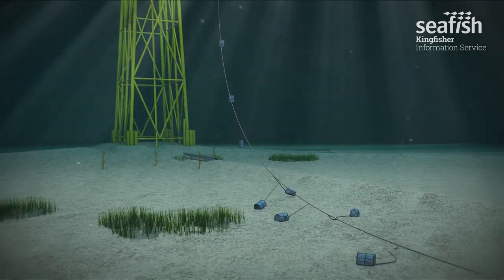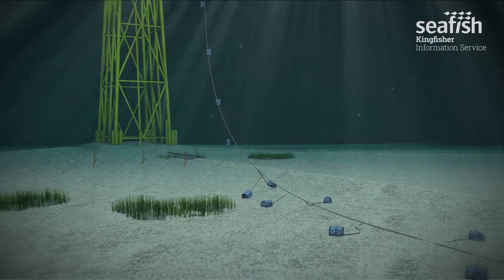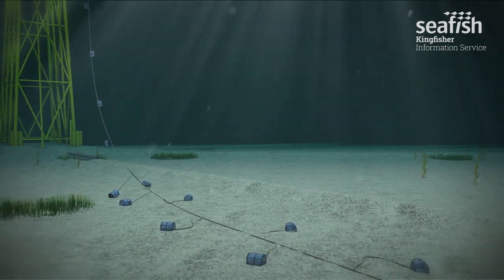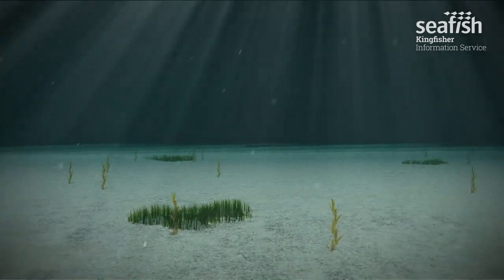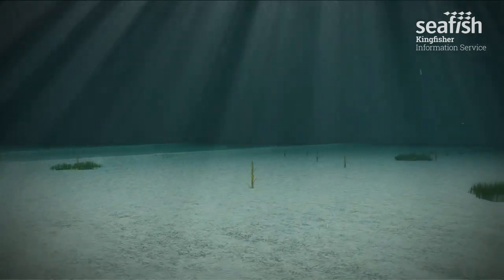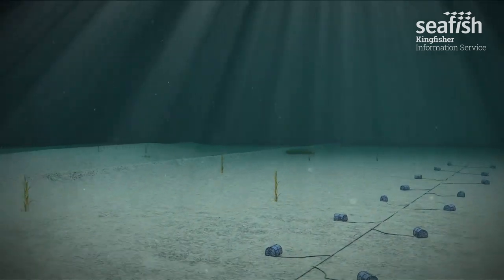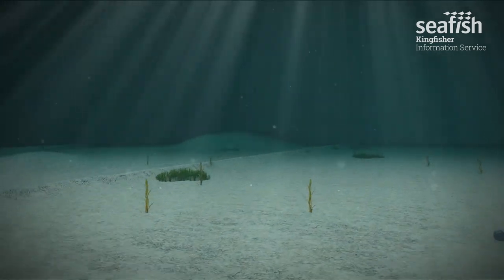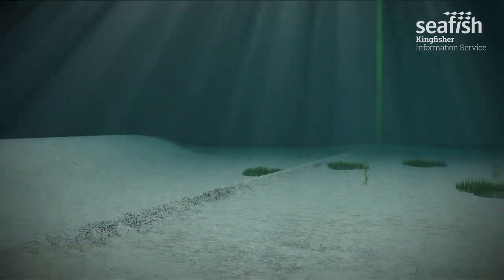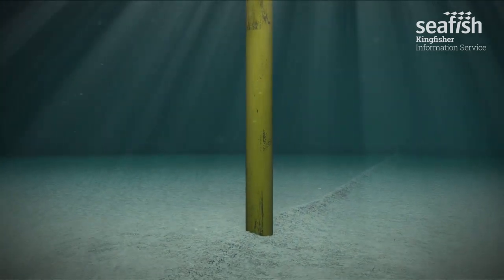An extensive network of cables installed within a wind farm link together each turbine. Generally, all cables within a wind farm, known as inter-array cables, will pass through an offshore substation before export cables take the power to shore. Wind turbines may be installed between 400 metres and 1,500 metres apart. Cables are commonly installed in straight lines between turbines, although this is not always the case. Burial is attempted upon installation; however, successful burial is not always possible, with exposed sections or cable spans possible within a development.